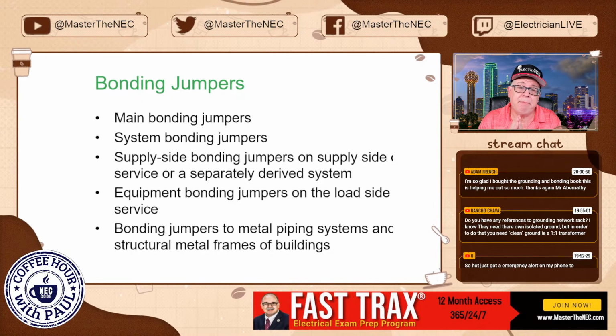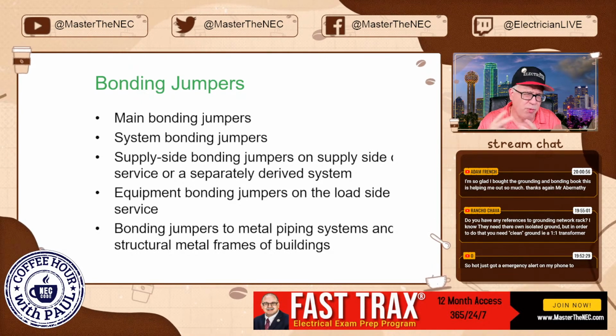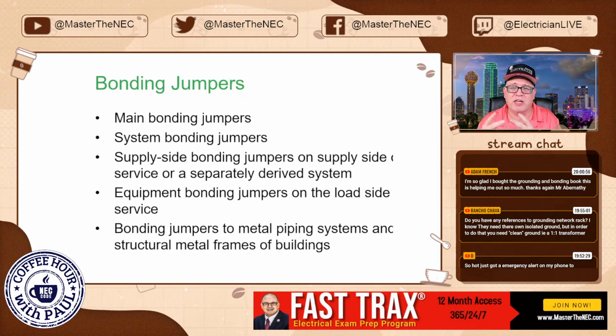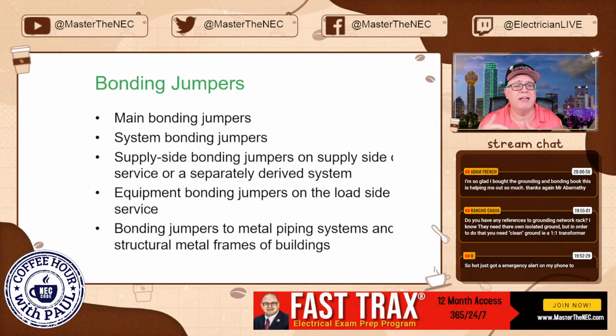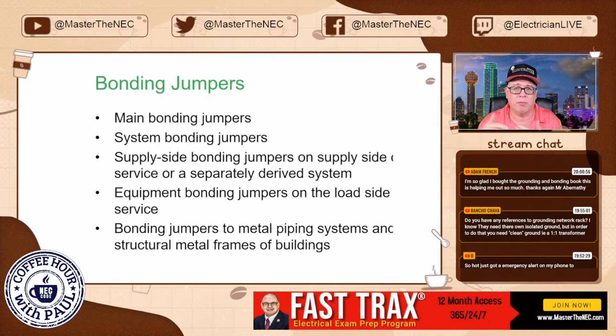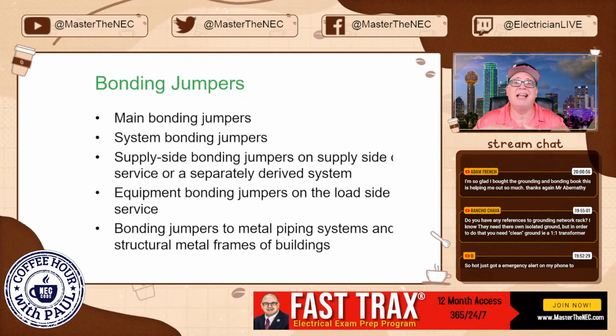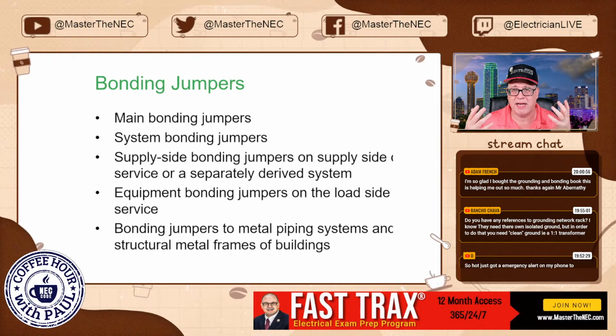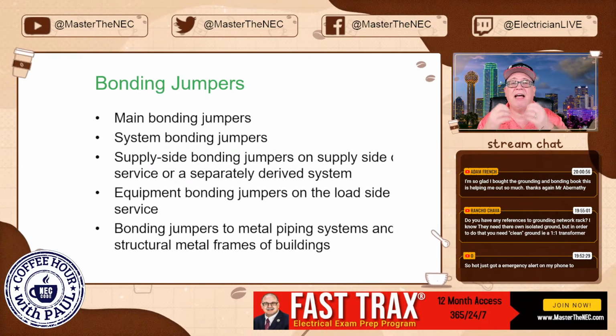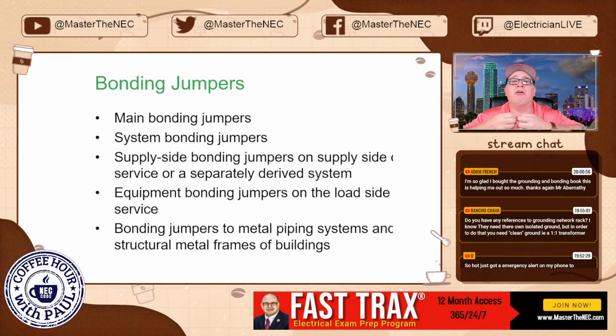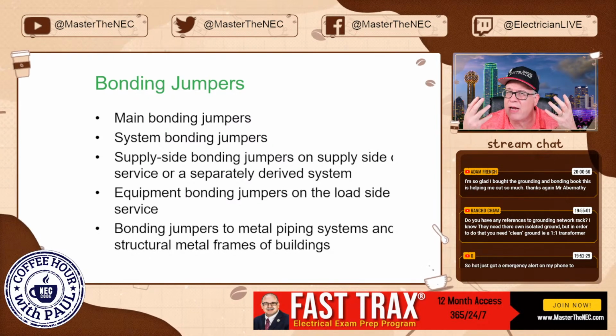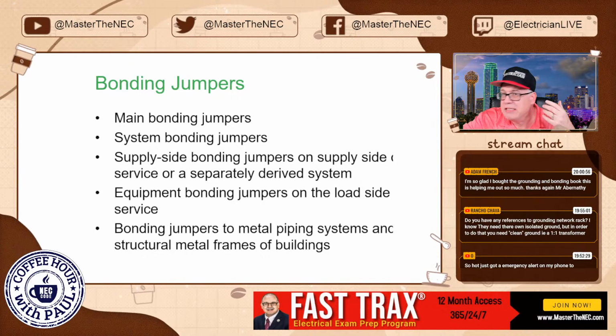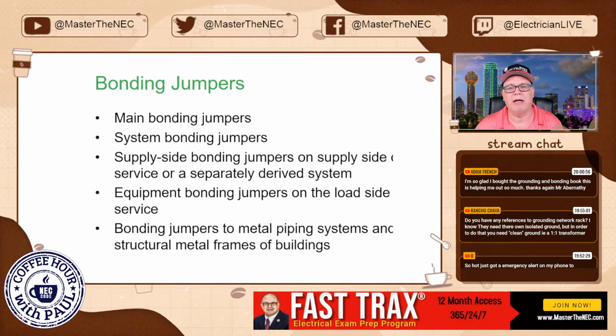Now, main bonding jumper and system bonding jumper perform the same function, right? Allow that current to get back to the source to clear an overcurrent device, whether it's a transformer, whether it's a generator, whether it's a utility. It allows that fault current to get back, okay, complete the circuit, and allows it to have a low impedance path, so it allows that fault current to skyrocket. And what happens to the breaker when that happens? It clicks quick, and that's what we're trying to achieve.